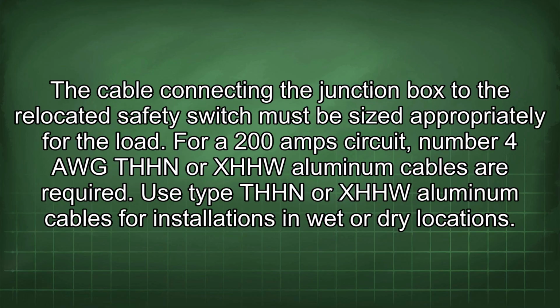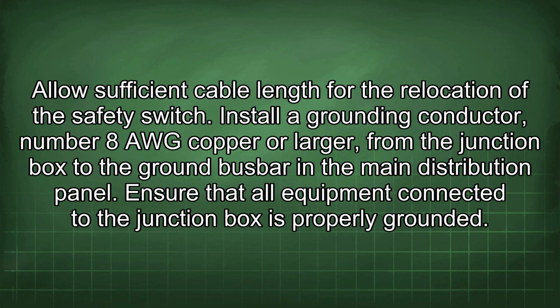The cable connecting the junction box to the relocated safety switch must be sized appropriately for the load. For a 200 amp circuit, number 4 AWG THHN or XHHW aluminum cables are required. Use type THHN or XHHW aluminum cables for installations in wet or dry locations. Allow sufficient cable length for the relocation of the safety switch. Install the grounding conductor, number 8 AWG copper or larger, from the junction box to the ground busbar in the main distribution panel. Ensure that all equipment connected to the junction box is properly grounded.